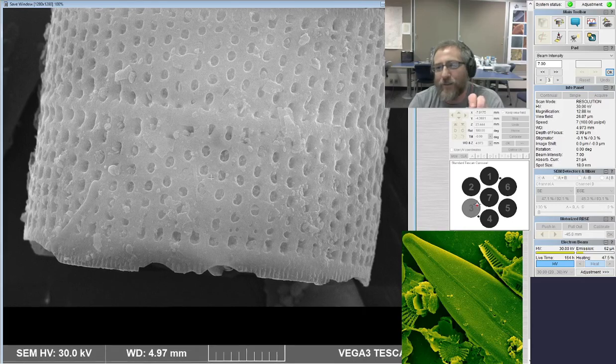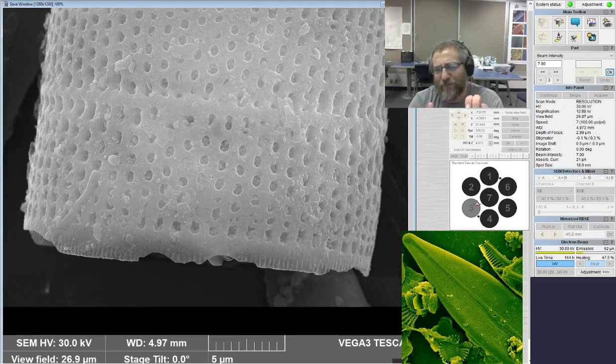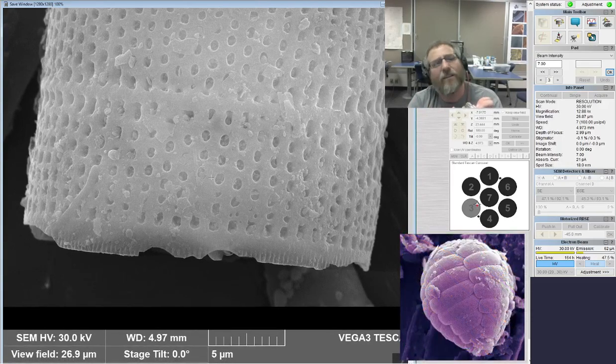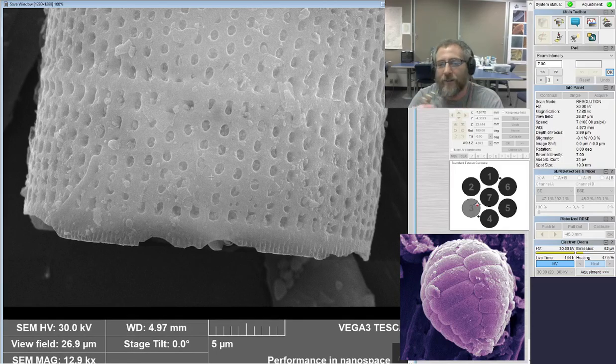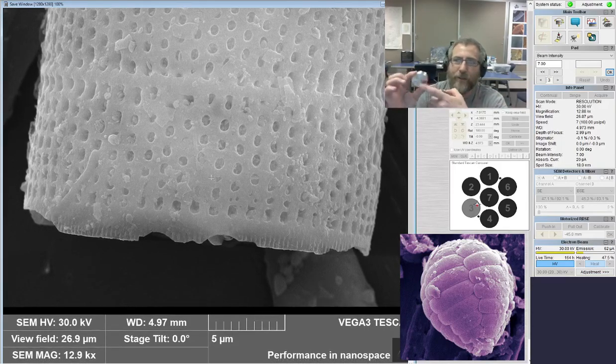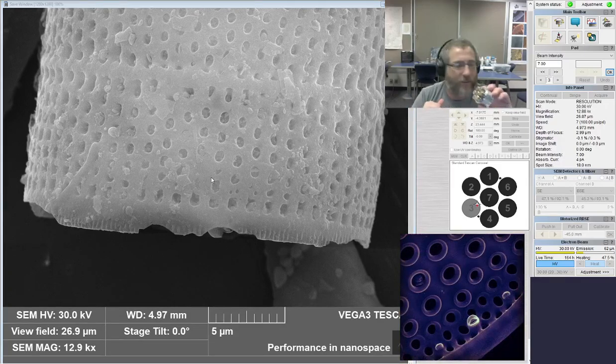So for reference, inside the SEM, if you're wondering how big those stubs are, they're 12.5 millimeters across, I think, and about 10 millimeters high. And that's the carousel that you're seeing. It just sits on a pin, and each one of these has a little pin as well that it sits in on the carousel. So they're sort of T-shaped stubs. They're like this, and then there are little holes that they just sit in.